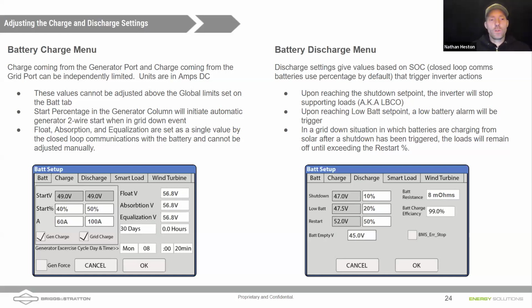So the left column corresponds to charging from the generator port, not necessarily a generator, but a generator port. And then the right column that you see there is charging sources connected to the utility port or the grid port. So you might have your generator connected to the utility port. In that case, Daniel, how would I program in settings that I want to use with my generator? You would use the right-hand column there. The right column for the grid port, right? Exactly. So again, these refer more to the physical location than the device that's being used for the power.